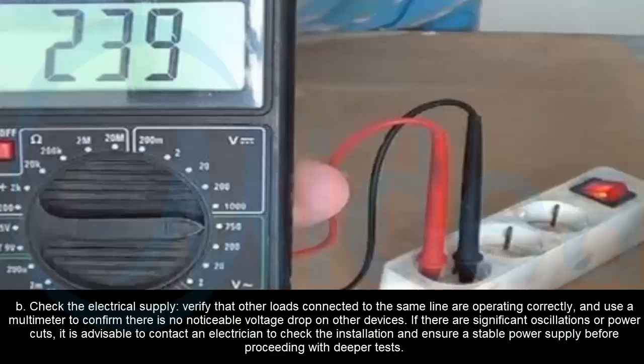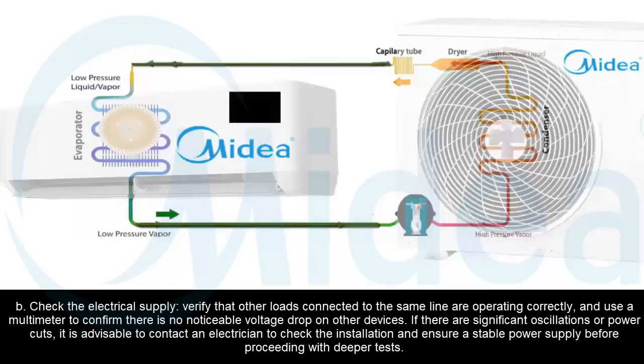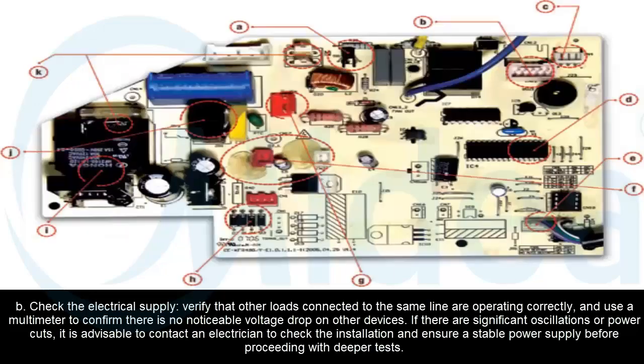B. Check the electrical supply. Verify that other loads connected to the same line are operating correctly and use a multimeter to confirm there is no noticeable voltage drop on other devices. If there are significant oscillations or power cuts, it is advisable to contact an electrician to check the installation and ensure a stable power supply before proceeding with deeper tests.